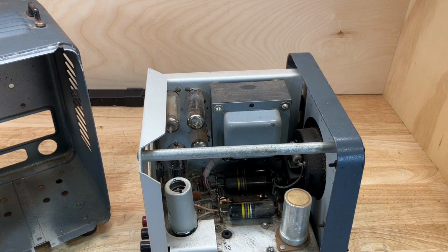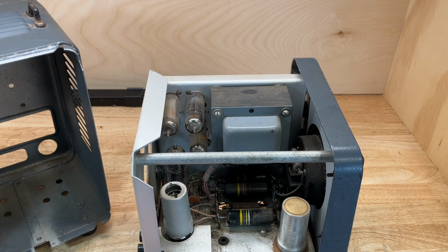But something might be causing a problem, because we have the wrong fuse inside this instrument. We've got a big electrolytic can here. I'll test that to see if there's any leakage or shorts or anything in that.